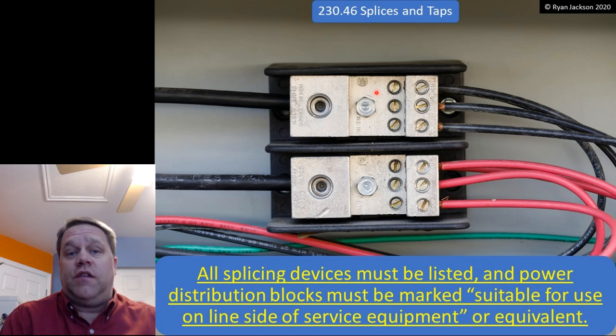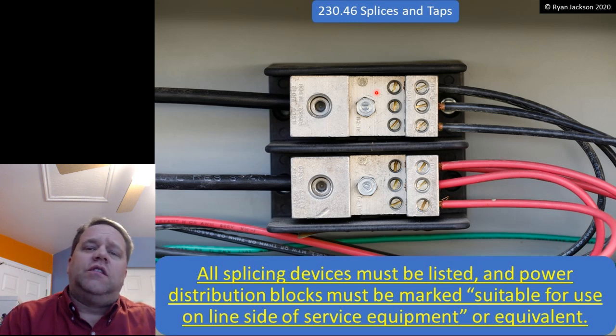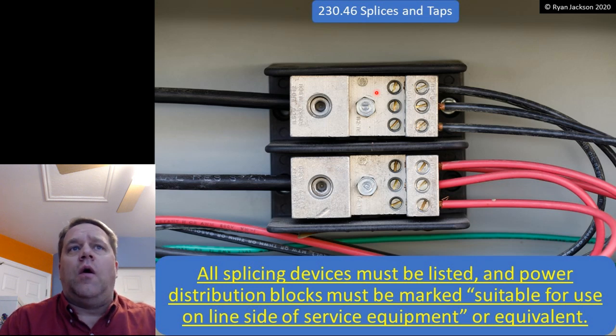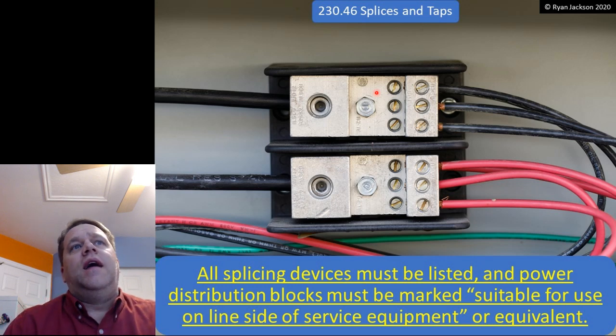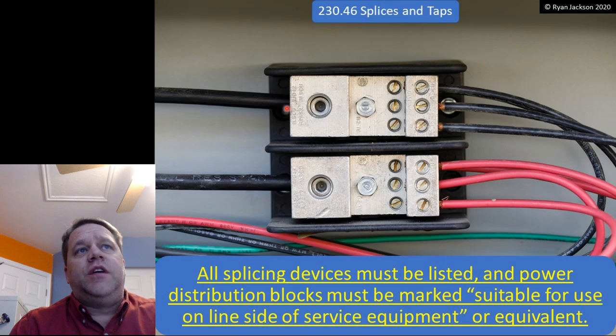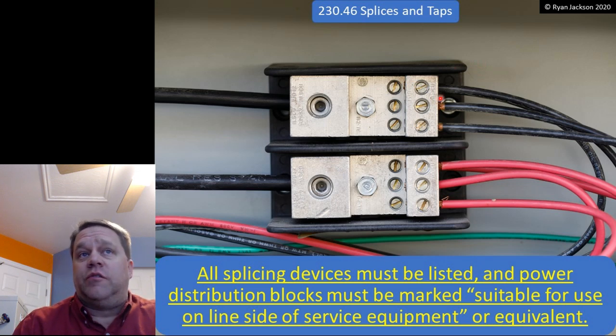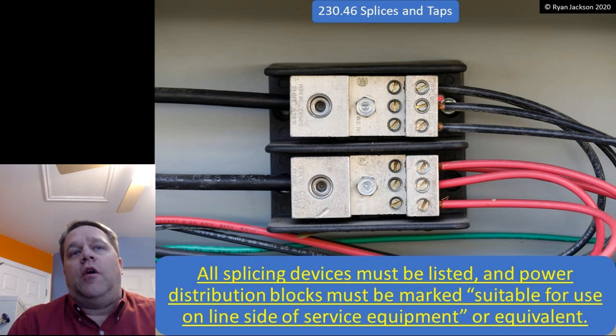There's a lot of things in the NEC that do not have to be listed, but splicing devices for service conductors now must be listed products. And for this particular type of product, a power distribution block, it has to be marked suitable for use on the line side of service equipment or equivalent.